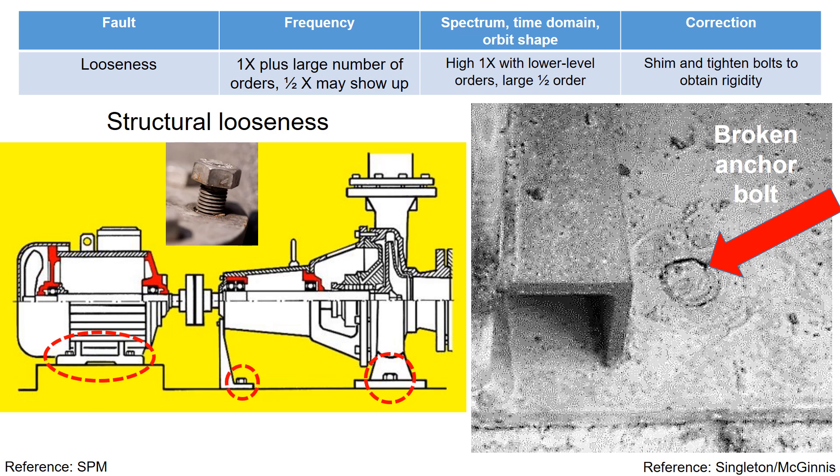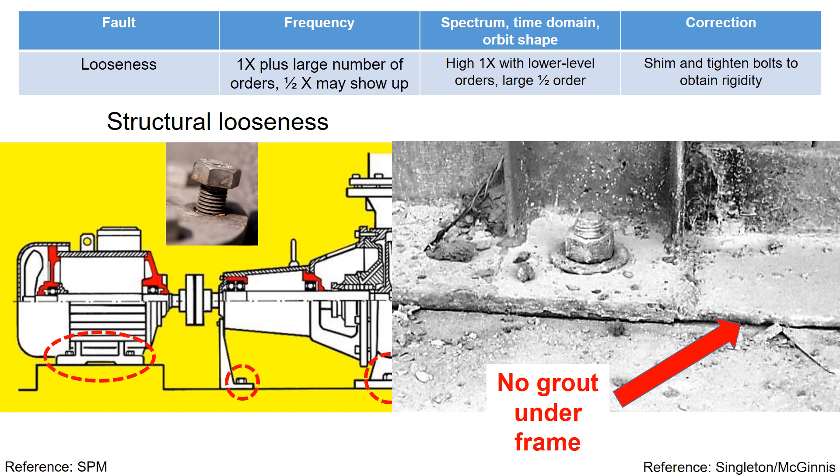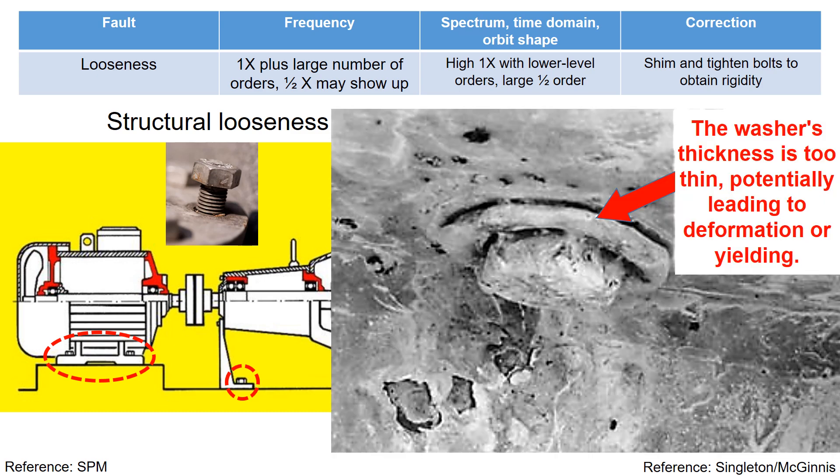Structural looseness can manifest in various ways, including broken anchor bolts. Also, the absence of grout in the frame can lead to structural looseness. And the thinness of the washer may pose a risk of deformation or yield, potentially resulting in structural looseness.